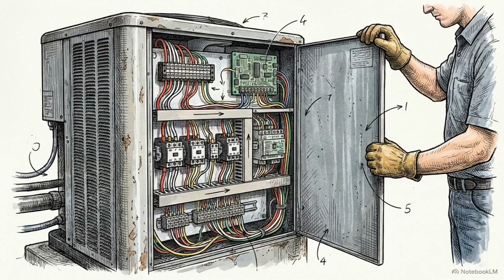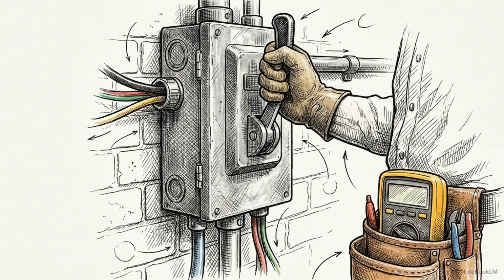Before making any electrical measurements, open the equipment cabinet and assess the physical condition of the unit. Turn off the line voltage to the system. Use your multimeter to verify that the power is entirely dead before you touch any low-voltage wiring.